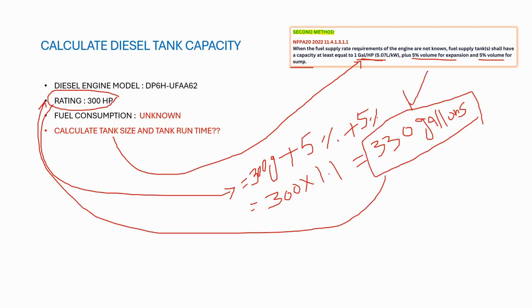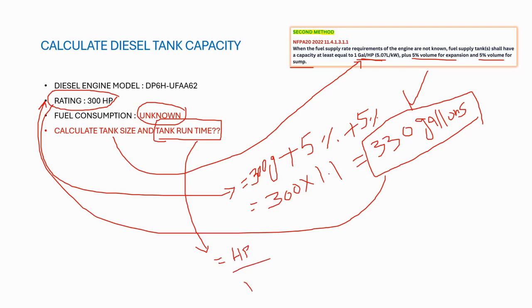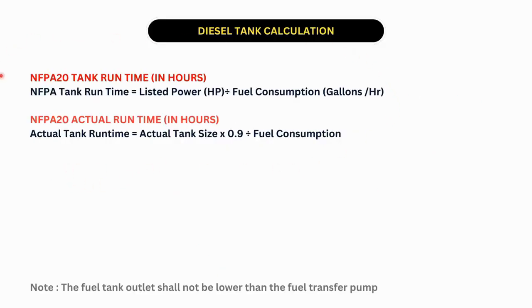An important point: when using Method 2, the tank run time cannot be calculated because we don't know the fuel consumption rate. The formula for tank run time requires engine horsepower divided by the fuel consumption rate. Since the fuel consumption is unknown, we cannot calculate the tank run time.